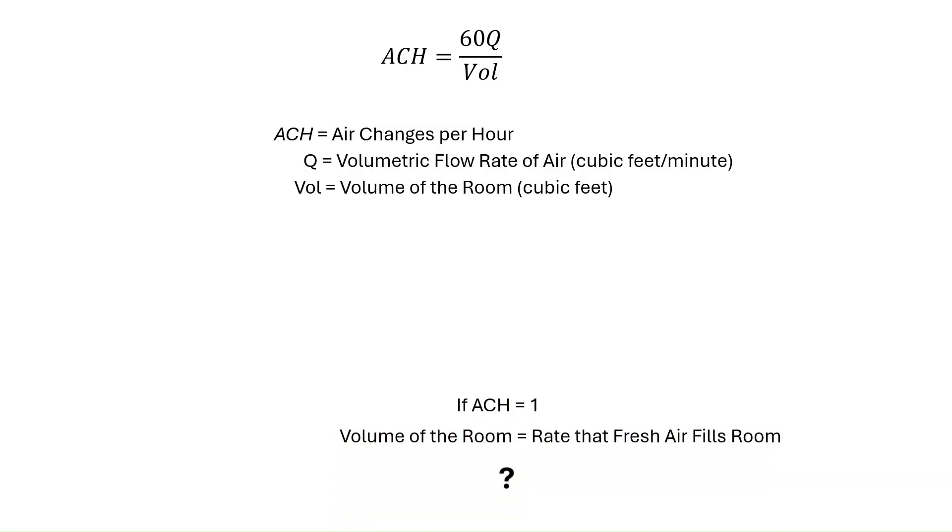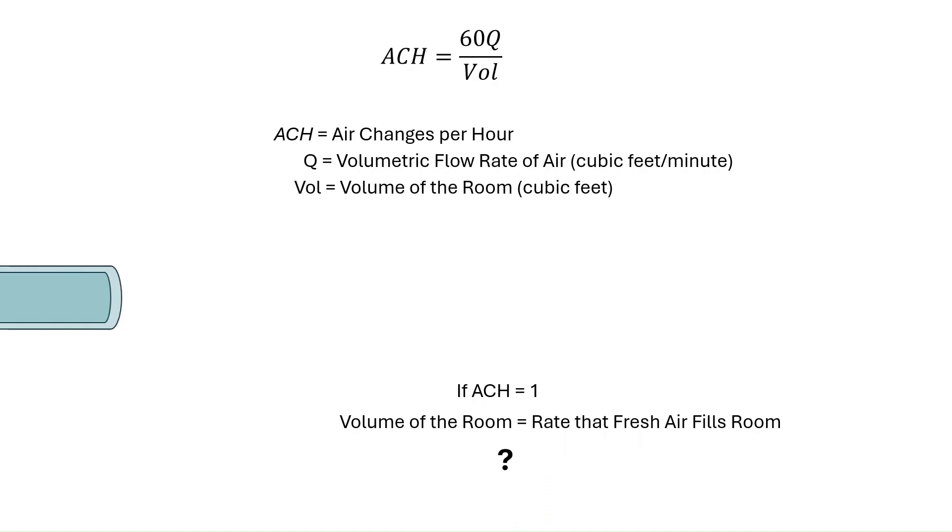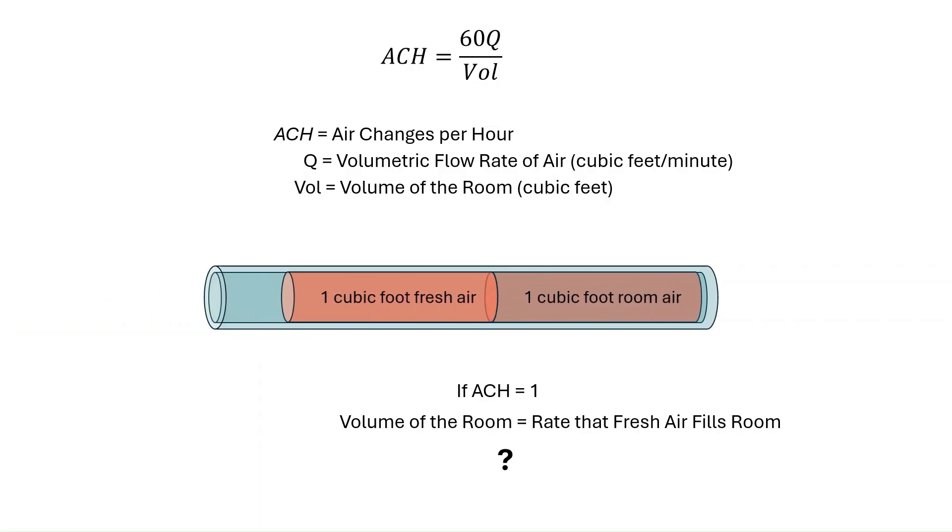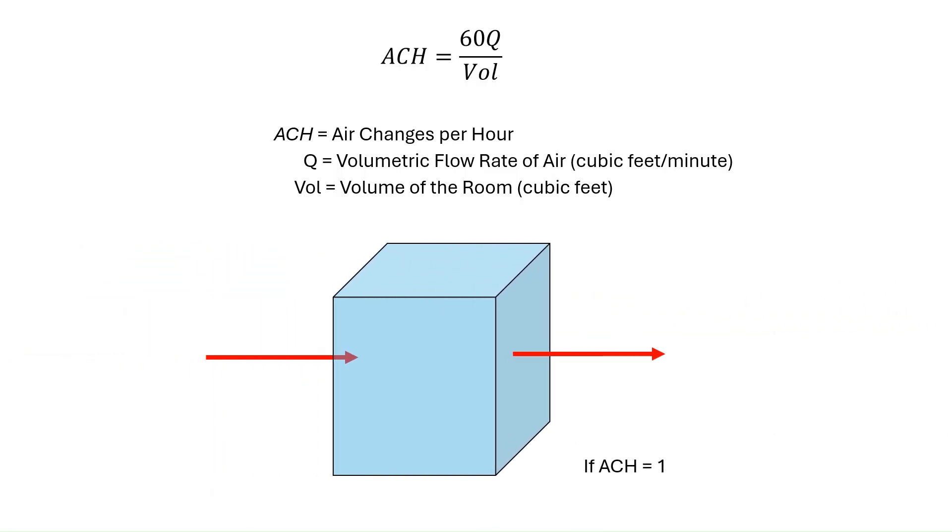Now, you would think that an ACH of 1 would mean that 100% of the air in the room would be replaced every hour. If the room was a pipe, this would be true. Every cubic foot of room air would be replaced by 1 cubic foot of fresh air added. However, for a room, this is just not the case. This is because the fresh air that's added to the room is mixed with the air already in the room, and thus only a fraction of the air is removed. As a result, an ACH of 1 actually means only about 63% of the air is removed per hour.